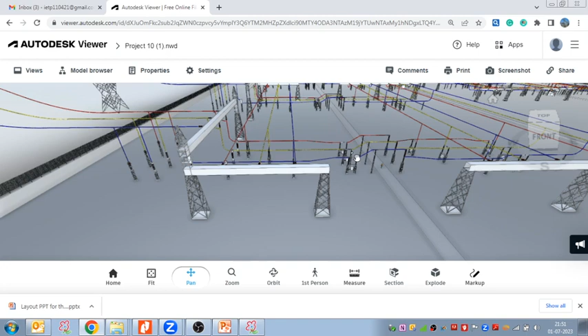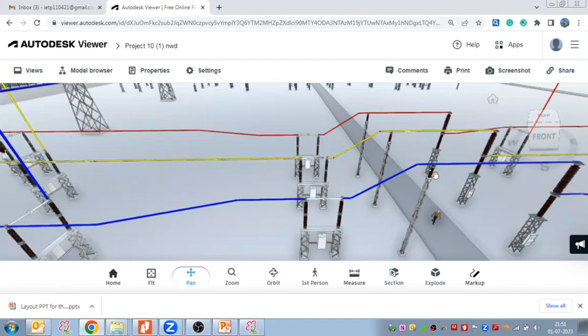Plus, if your substation is more than 132 kV, for above 132 kV the circuit breaker - this equipment you can see - its weight and size are too high to be handled manually, so we have to take additional equipment like a crane or erection machine to handle it. For that purpose also we have to plan a route near the circuit breaker for above 132 kV.